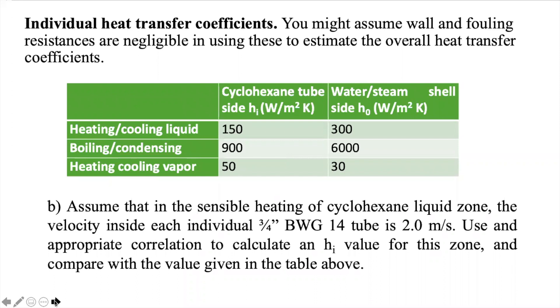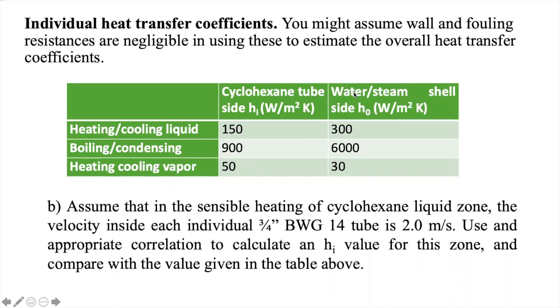Using a zone analysis hand calculation, we first estimate the total area required in m². We have given physical properties for cyclohexane and water steam: Cp liquid, Cp vapor, and enthalpy of vaporization for both streams. We are also given individual heat transfer coefficients, which simplifies the problem. The problem states wall and fouling resistances are negligible for estimating the overall heat transfer coefficient, so we only use the two convective terms. Boiling and condensing heat transfer coefficients are much higher when there is phase change.